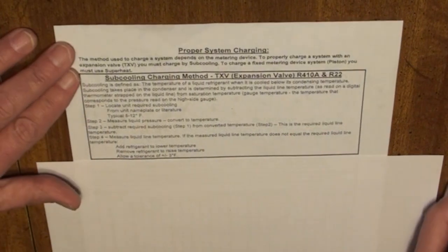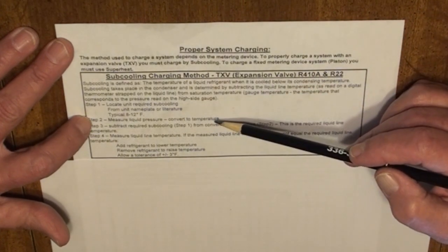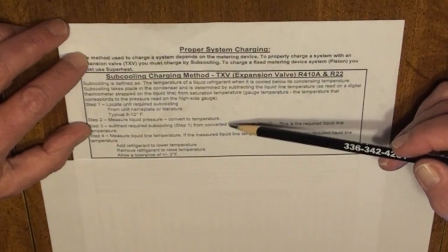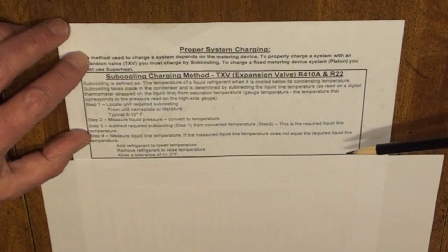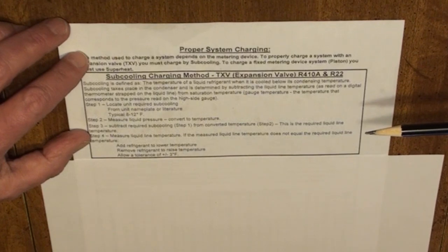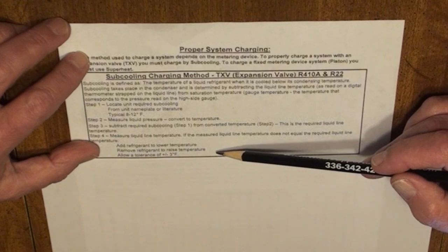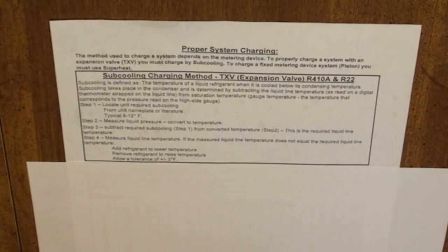According to our chart, from the unit nameplate or literature, an average subcooling is typically 8 to 12 degrees, though depending on which book you pick up, it may be as high as 20. Measure the liquid pressure and convert to temperature, then subtract the required subcooling to find the required liquid line temperature. Measure the actual liquid line temperature. If the measured liquid line temperature does not equal the required, add refrigerant to lower the temperature or remove refrigerant to raise the temperature. They allow plus or minus 3 degrees Fahrenheit to adjust the charge to a normal subcooling.